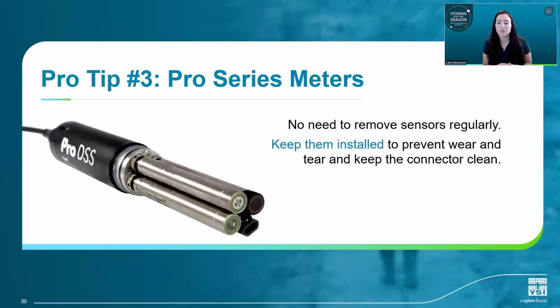If you have a Pro Series or other instrument with MIL-spec or LEMO connectors, here's my tip for you. You don't need to remove your sensors, like we said earlier, because they don't need the same maintenance and relubrication like the wet mates do. Of course, you can take them out if you need to swap sensors or for maintenance or specific sensor storage, or if you suspect an issue, but otherwise go ahead and keep them installed to prevent wear and tear of the connector, and also keep extra dirt or dust from getting into the ports.